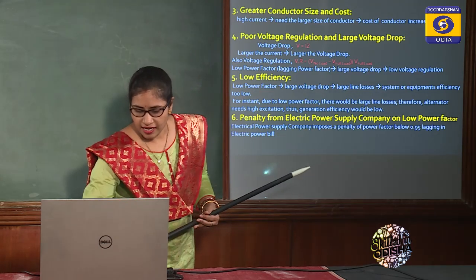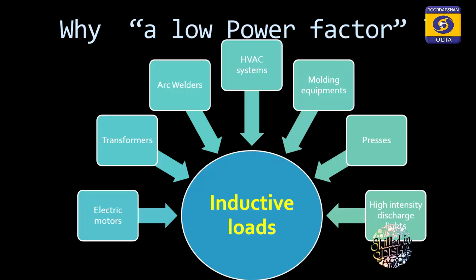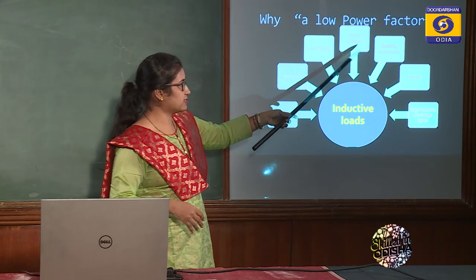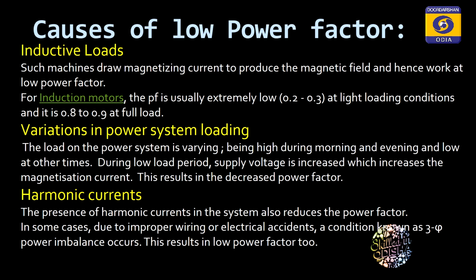The reason power factor becomes lower is inductive loads in the power system. These loads consume lagging current, which leads to a lower power factor. Inductive loads include a whole range of electric motors, transformers, arc welders, HVAC systems, molding equipment, presses, and high-intensity discharge lights. Basically, it is the inductive load that makes the power factor lower by consuming lagging current.